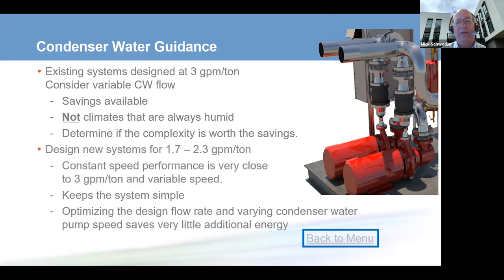If it's a new plant though, and you design it for the 1.7 to 2.3 GPM per ton, you're already in an optimal range. You can set and forget the condenser water pump speed, use a variable speed drive on it to balance the flow rate, but you don't have to have the complexity by selecting the proper system flow rate and delta T.